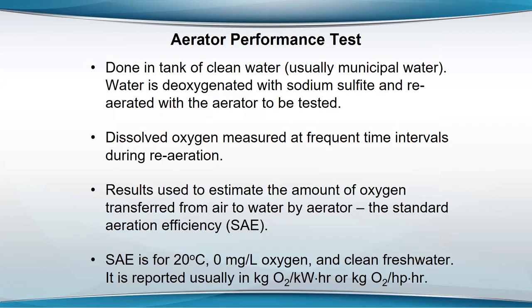The aerator performance test — to see how efficient these aerators are — is done in a tank of clean water, usually tap water. You deoxygenate the water with sodium sulfite, then re-aerate it with the aerator being tested. You measure the dissolved oxygen concentration over time while the aerator re-aerates the water in that tank.